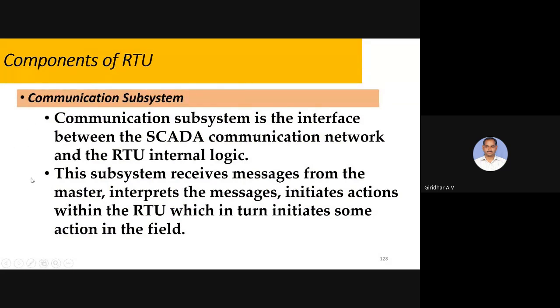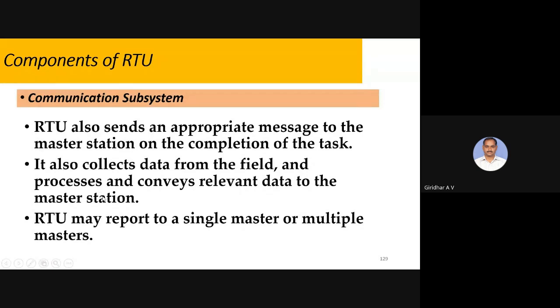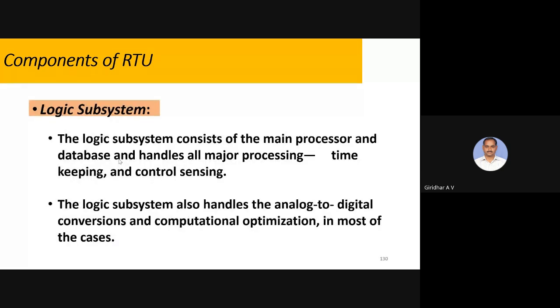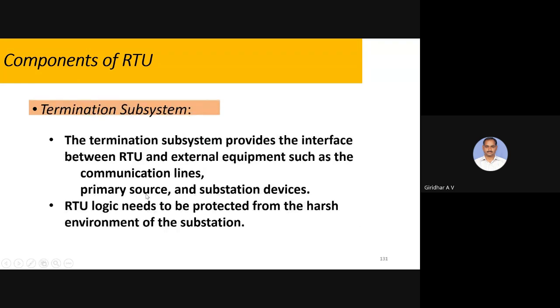So these are the communication subsystems in the RTU. The RTU also sends an appropriate message to the master station for completion of the task. It also collects the data from the field, processes it, conveys relevant data to the master station, and reports to a single master or multiple masters. In the logic subsystems, mainly the database, major processing, timekeeping, and control sensing are done. Analog to digital conversions and computations are also done in the logic subsystems.